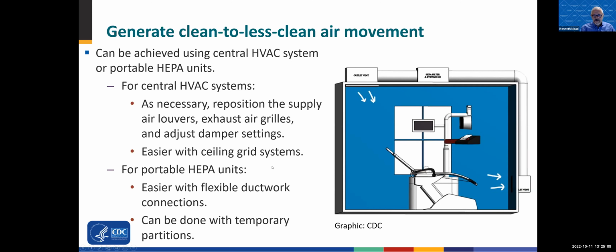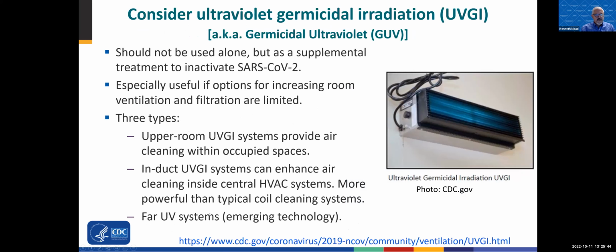You can do the same thing with your central HVAC, especially if you have a ceiling grid type system that allows you to position your supply and return. You can do similar strategies. Think about things like the reception desk or the check-in desk at a healthcare facility, for instance. You might have it so your clean air is coming in from behind the receptionist and going out across towards the waiting area. For portable HEPA units, you can do this a little bit easier if you have flexible ductwork connections. You can also augment the airflow directions using partitions.